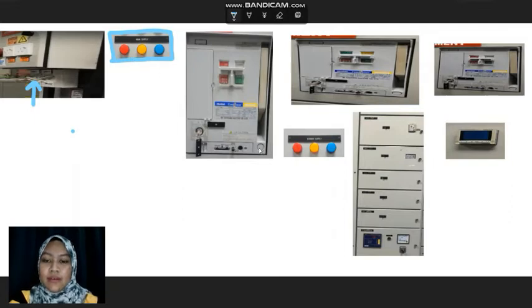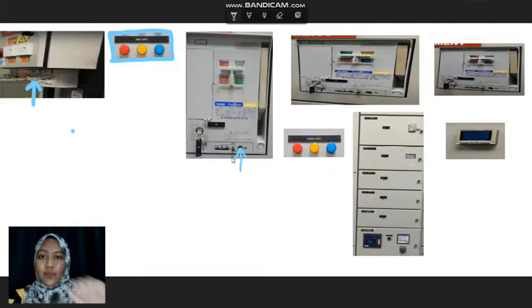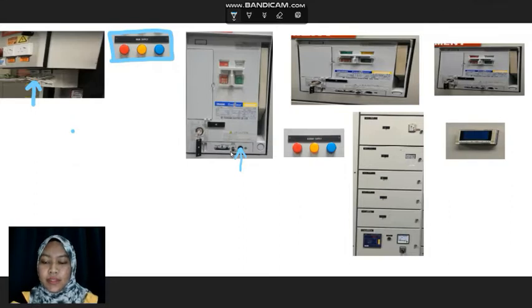After that, we need to connect the air circuit breaker. We will connect the air circuit breaker to the bus bar using the charging handle inside the air circuit breaker compartment. First, we insert the charging handle inside the slot here, and then we turn it clockwise until the air circuit breaker is in connect position. After the air circuit breaker is connected to the bus bar, remove the charging handle and put it back inside the air circuit breaker compartment.